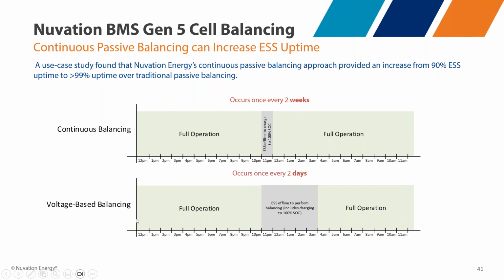Comparing that with voltage-based balancing, you have to hold the system at this higher state of charge in order to do voltage-based balancing, and you really should be balancing the system every couple days. So continuous balancing gives you more than 99% uptime, whereas with traditional voltage-based balancing, you can take as much as 10% of the system time.